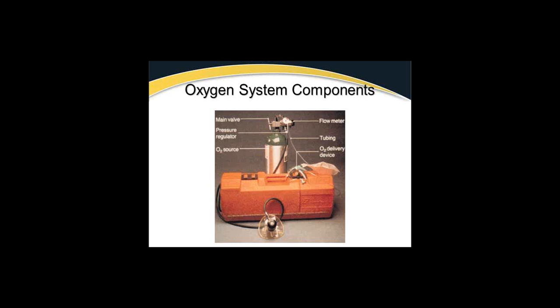Now, also on page 220 in your textbook, it shows you the oxygen bottle laying down. That is the safest position for that bottle to be in. If you have an oxygen bottle sitting up and it gets knocked over and the neck or the valve gets damaged, that pressurized bottle becomes a lethal rocket. That little D tank, you break the neck off of it, it will shoot through a cinder block wall. So it is dangerous.